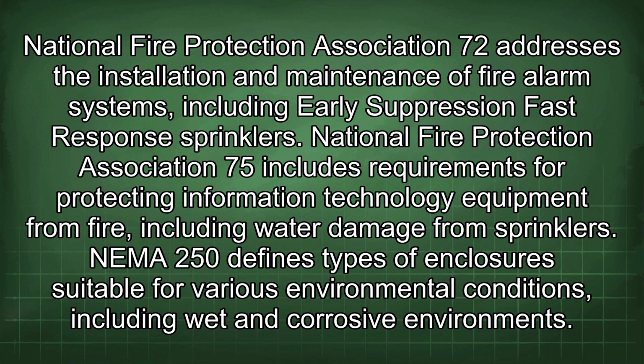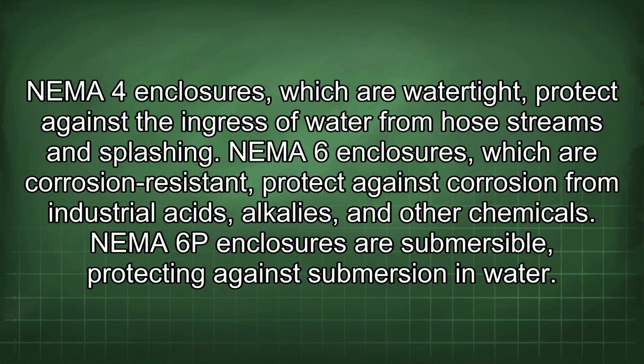National Fire Protection Association 75 includes requirements for protecting information technology equipment from fire, including water damage from sprinklers. NEMA 250 defines types of enclosures suitable for various environmental conditions, including wet and corrosive environments. NEMA 4 enclosures, which are watertight, protect against the ingress of water from hose streams and splashing. NEMA 6 enclosures, which are corrosion-resistant, protect against corrosion from industrial acids, alkalis, and other chemicals. NEMA 6P enclosures are submersible, protecting against submersion in water.